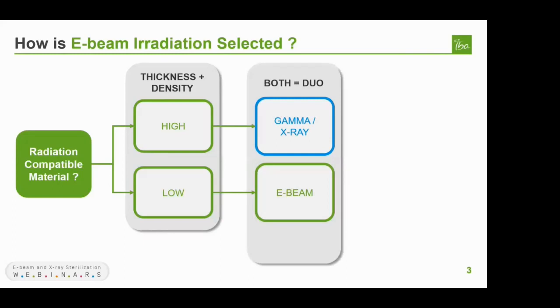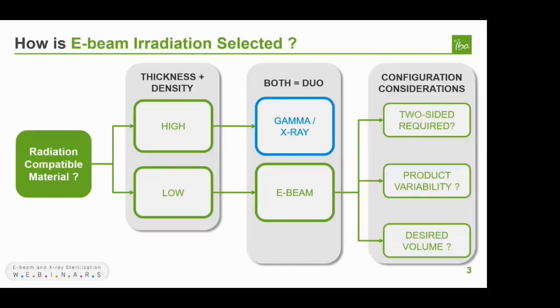If the products are considered high by the thickness and density metric, gamma or X-ray sterilization is appropriate. If the answer is low, e-beam sterilization is a good candidate. If there's a mix of high and low products, systems capable of sterilizing with both e-beam and X-ray are available.